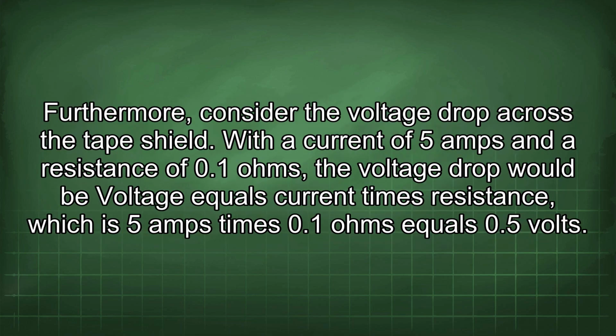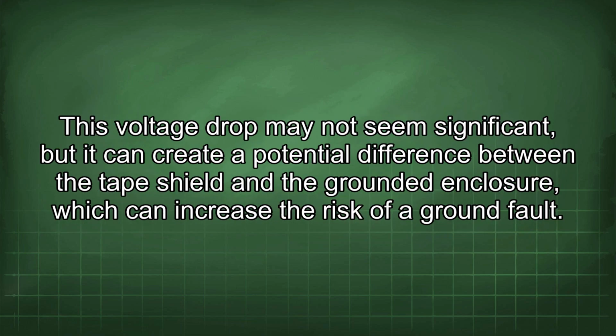Furthermore, consider the voltage drop across the tape shield. With a current of 5 amps and a resistance of 0.1 ohms, the voltage drop would be voltage equals current times resistance, which is 5 amps times 0.1 ohms equals 0.5 volts. This voltage drop may not seem significant, but it can create a potential difference between the tape shield and the grounded enclosure, which can increase the risk of a ground fault.